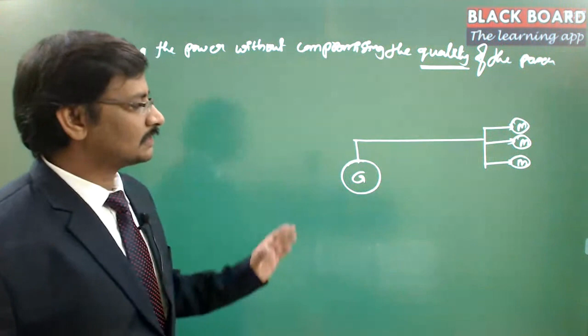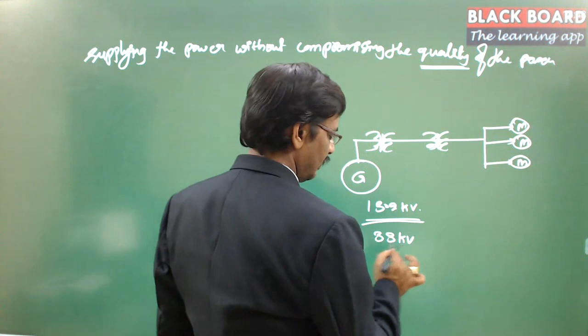These transformers come into picture because the generating station usually generates a very small voltage, around 13.2 kV, or sometimes up to 33 kV, not higher, because the insulation capacity needed for the generator is very costly.